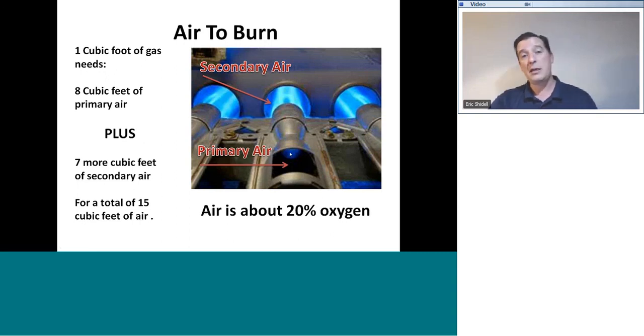This mixing of air with fuel causes there to be a combustible mixture. Without that air mixture, gas will not burn. If that mixture is too lean, as in not enough air to mix with the fuel, it won't burn. If it's too rich, that would be too much fuel, not enough air. If it's too lean, there's too much air and not enough fuel, it won't burn either. It has to be a very specific mixture of fuel to air to create a flammable mixture.